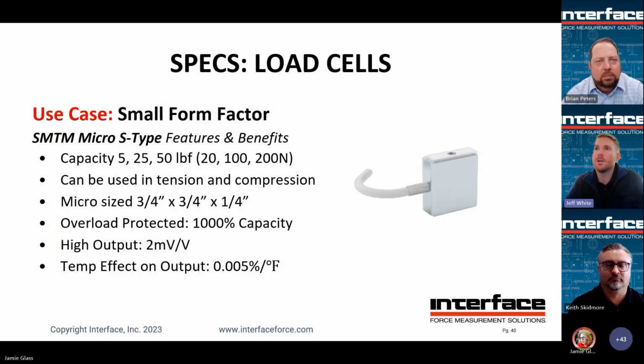Next slide. So now we get into the small form factor. The SMTM Micro S-Type Mini is a very popular model that can fit into some of the smallest medical, test and measurement, and industrial applications we encounter. You can see the size there. Another one to note is the overload protection, 1,000% of the capacity, while still offering a 2 millivolt per volt output, and it boasts a very robust temperature spec.